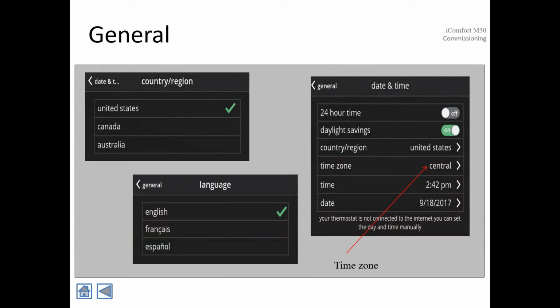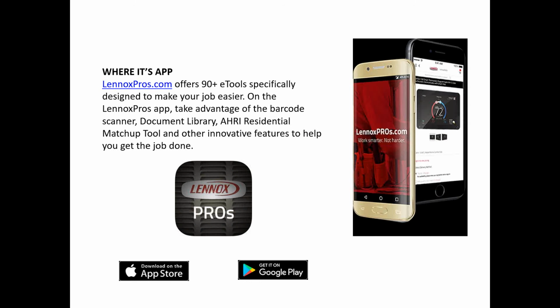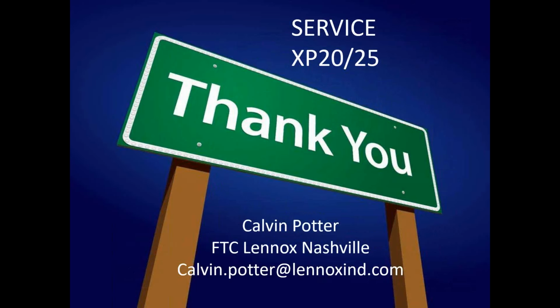All right, I know you had some M30. One thing I get several phone calls on is when that M30 first comes up, the smaller control stat that I think you'll be selling with the lower end stuff, maybe the 16, and for sure the 14. It asks for the time zone, which we don't have a problem with in Huntsville since we're on Central Time Zone, but I have some guys in East Tennessee where this comes up. Daylight savings time adjustment is on here. Once you set this up, this screen goes away. You cannot get back to it unless you do a hard reset. For whatever reason, that's just the way it is. So for my guys in East Tennessee, it's a big deal. We talked about the app a little bit, and we'll move on from these because we're running short on time.